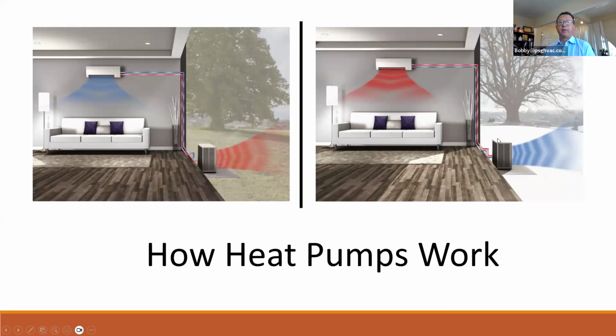Thank you, Nick. So, to recap how these heat pumps work. On the left is the summer season in heat pump operation, where we're expelling the heat from the space that's cooling down the space. On the left-hand side, the heat is being rejected to the atmosphere outside. On the left-hand picture, you see the red discharge, which is going to be the heat. Now, how heat pumps also work on the right side is just a mere reversing valve of the refrigerant. So on the right side, utilizing the reversing valve, we're harvesting the ambient heat in the air and pumping that into the space using the same system.